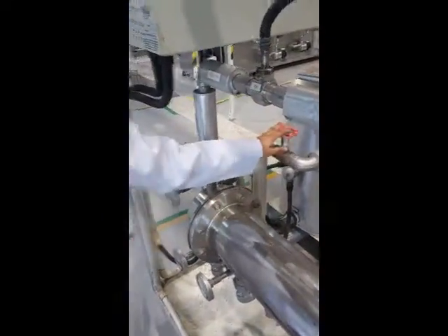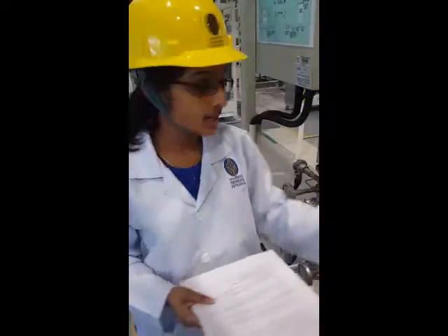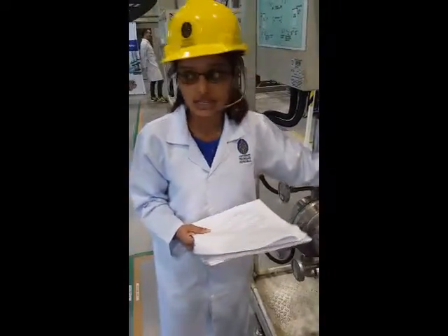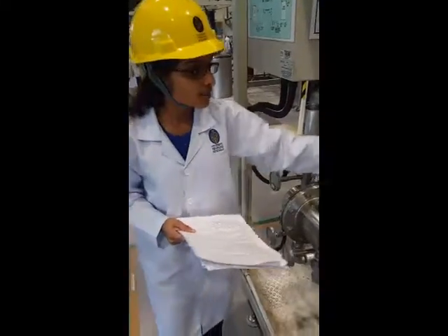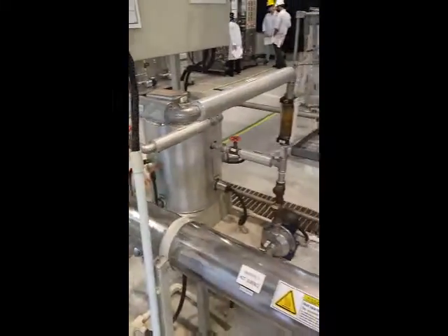And you have to change the hot water flow rate according to your trial. So first we set the cold at 20 liter per minute, and the first reading starts from 4 liter per minute for hot water flow rate. Once you have set it to 4 liter per minute, get back here to get the reading.